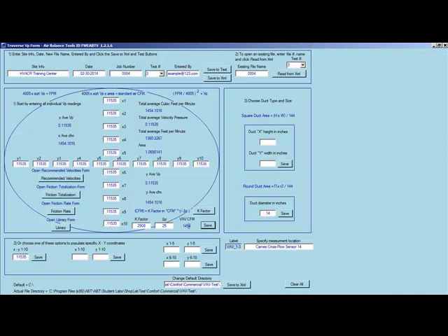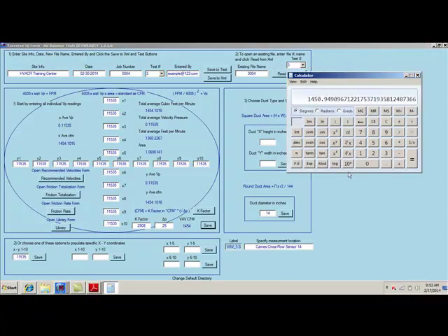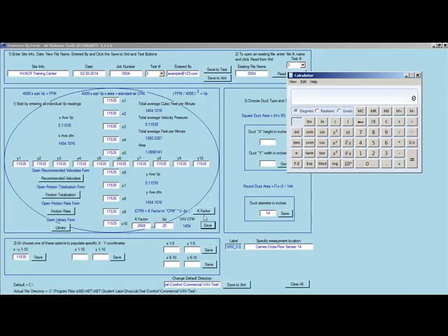And in this case we're getting 1454. So on the lowest end of the scale we can say 3 times 100 divided by 1454, and we're at a percentage of 0.2, which in most cases sensors are plus or minus 2%, and we're at 0.2 at the lowest end of this scale.